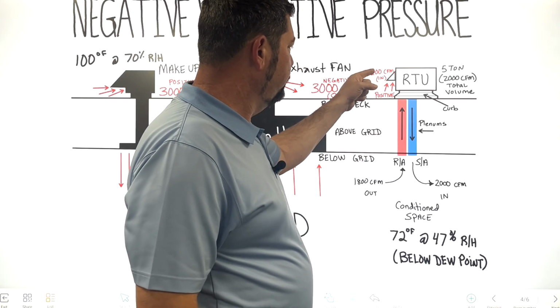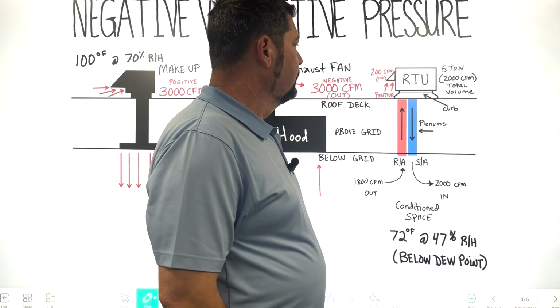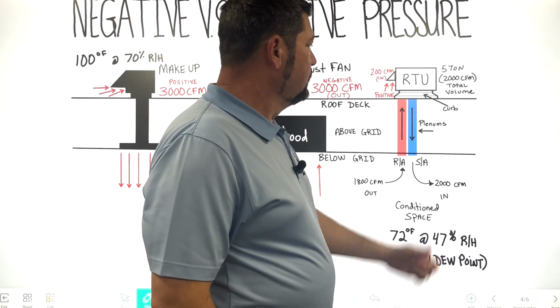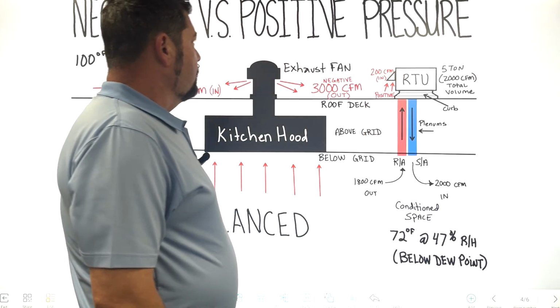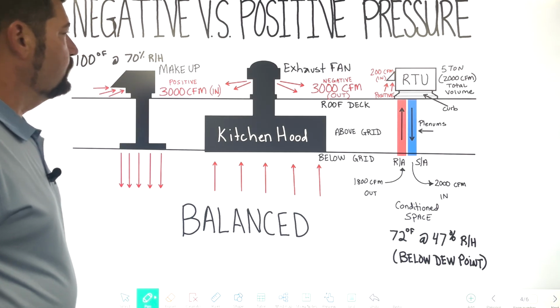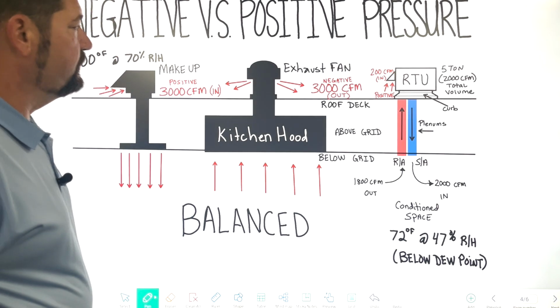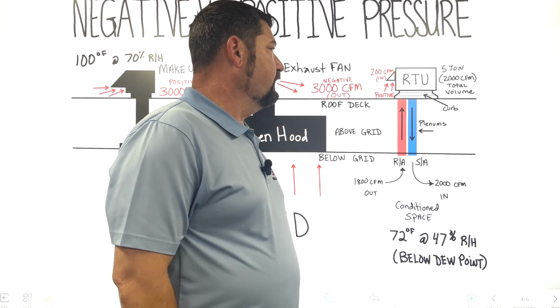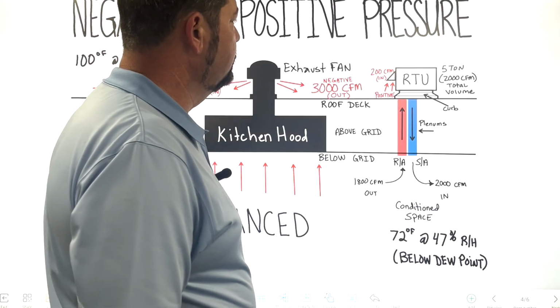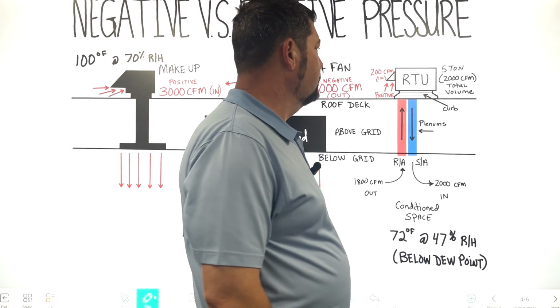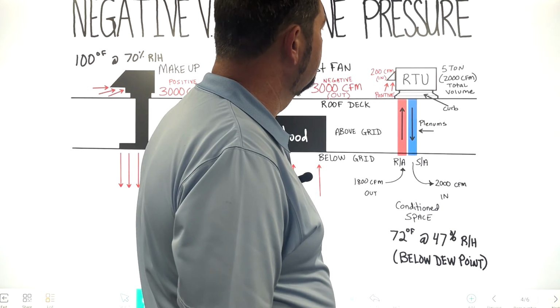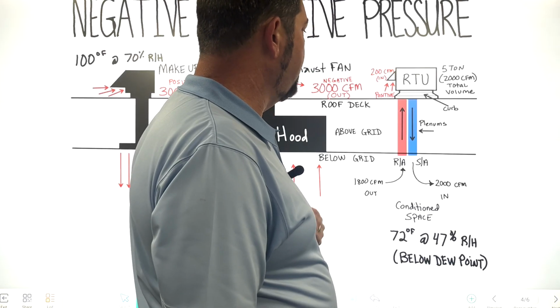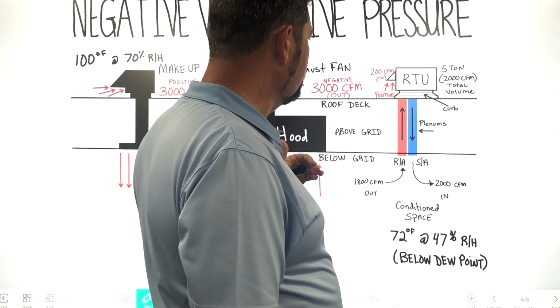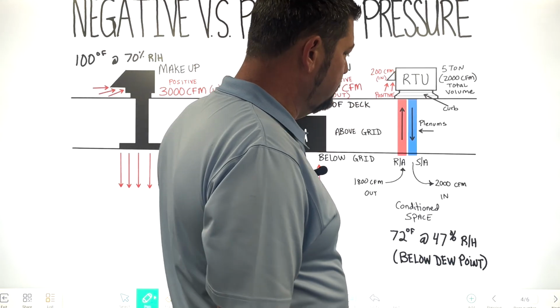So 1800 plus 200 equals 2000 on a 2000 CFM RTU. 5 ton or whatever the tonnage is. If it's a 10 ton, it's 4,000 CFMs. If it's a 20 ton, it's 8,000 CFMs. If I'm doing that, yeah. So at the end of the day, it doesn't matter what it is. You don't want too much, and you don't want not enough.